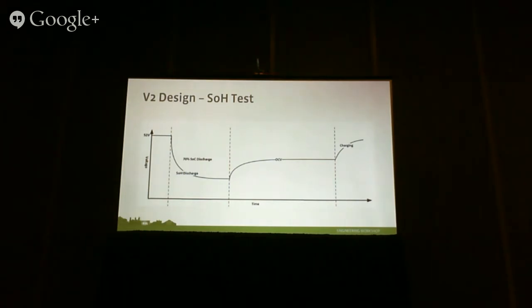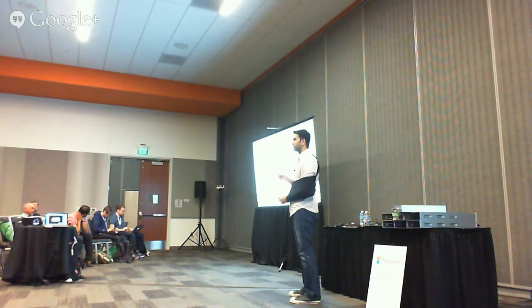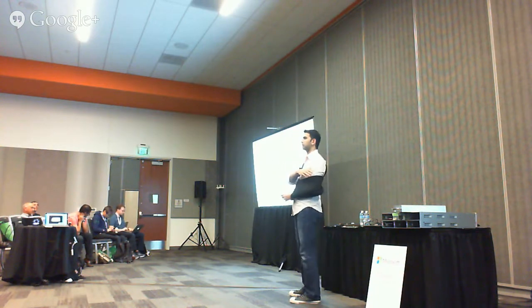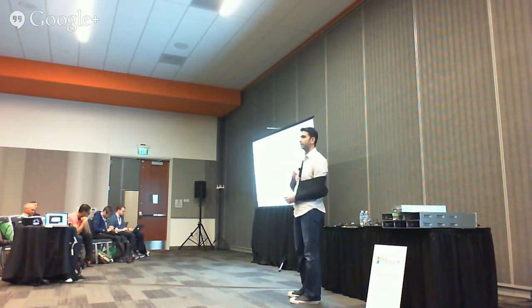But in our case, if we're doing 80 to 90% discharge, that basically means we're depleting the battery, and that translates to having no redundancy on the battery. We didn't want that. So we changed this slightly by only doing a 30% discharge on the battery for each test. That would ensure that during or after a test, if there's an outage, the cell can still sustain it.